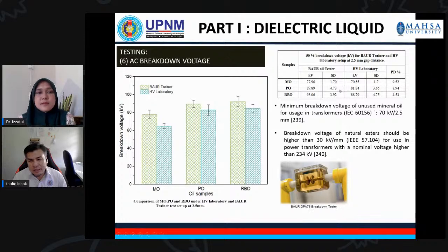So based on the results that we have, in both testing using the BAUR tester and using the high voltage laboratory, the rice bran oil performed very well for both tests. The first one you can get around 93 kV for 2.5 mm, and the other one is 88.79 kV for 2.5 mm. All the oils passed the requirement by the standard, which is more than 30 kV per mm, as you can see here. So this means that based on this result, the vegetable oil shows some promising results in terms of the AC breakdown voltage, and it surpassed the standard and is also better than mineral oil in this study.